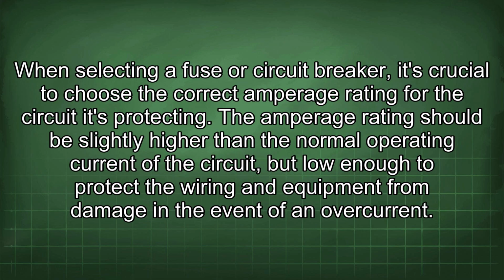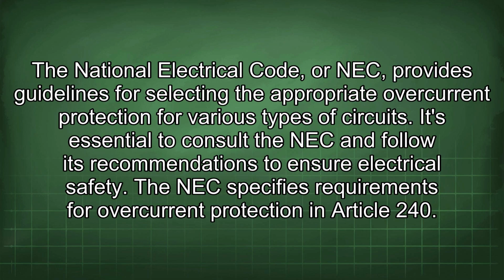When selecting a fuse or circuit breaker, it's crucial to choose the correct amperage rating for the circuit it's protecting. The amperage rating should be slightly higher than the normal operating current of the circuit, but low enough to protect the wiring and equipment from damage in the event of an overcurrent. The National Electrical Code, or NEC, provides guidelines for selecting the appropriate overcurrent protection for various types of circuits. It's essential to consult the NEC and follow its recommendations to ensure electrical safety.